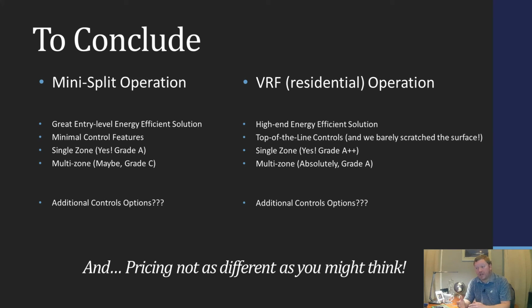On the VRF side, I also put, do you have additional controls options? Because there are more and more different controls options coming out that provide more features, but from a functionality standpoint, you don't need them. The thermostats that typically come with a VRF system, you're not getting the handhelds, you're getting an actual hardwired controller, and they have all of the functionality built in to give you all of the control we talked about today. And again, just remember, brands have differences, so the numbers we talked about today aren't all going to be identical from manufacturer to manufacturer, but a lot of them are very, very close and very, very similar.